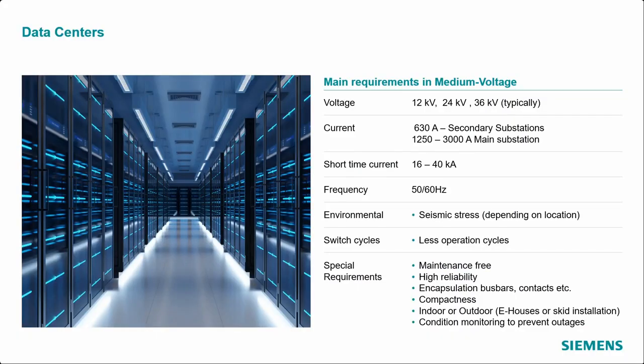Data centers, for example, is an application which manages big data as well as uncountable online processes. For that, the medium voltage switchgear in data centers needs to be reliable and provide a redundant power distribution in order to ensure continuous power supply and minimize downtimes, which is very critical for data integrity. Switchgears need to be also expandable to support scalability as power demand increases.